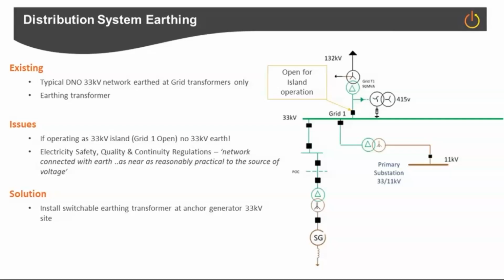So the solution is to install a switchable earthing device at the anchor generator 33 kV site. So a small earthing device that you can switch in or switch out, and to install at that anchor generator site. So that's something else we found.